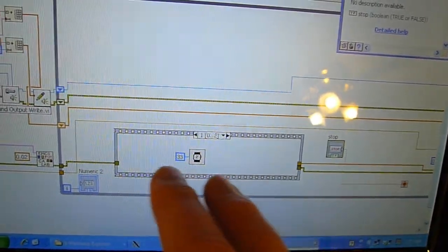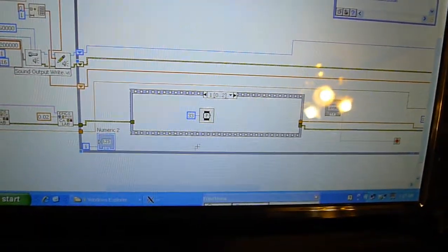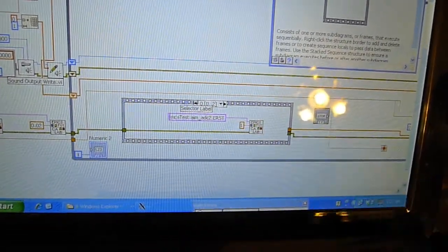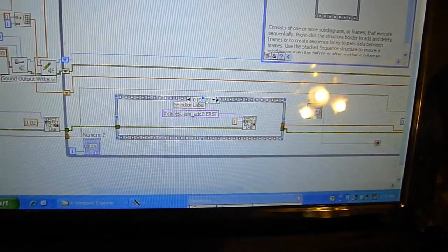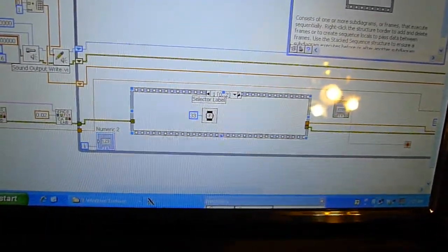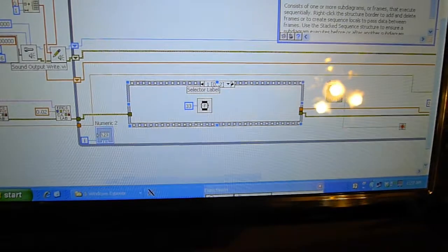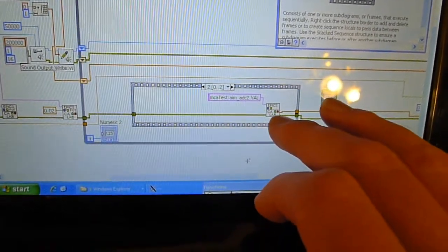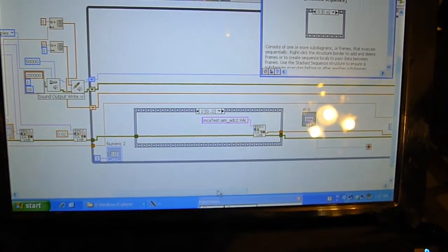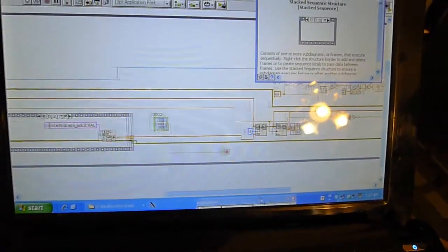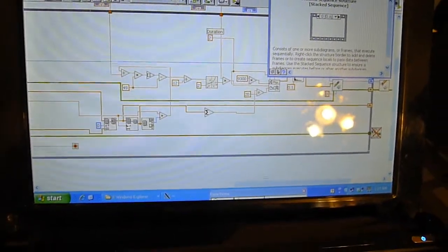And the first thing in the loop is this delay. After the MCA is told to erase its memory and start, we have to provide a delay so that it can go ahead and finish collecting that data and transferring it. That's this step. Then we ask it to send the array of data, in other words, counts versus channel, out.